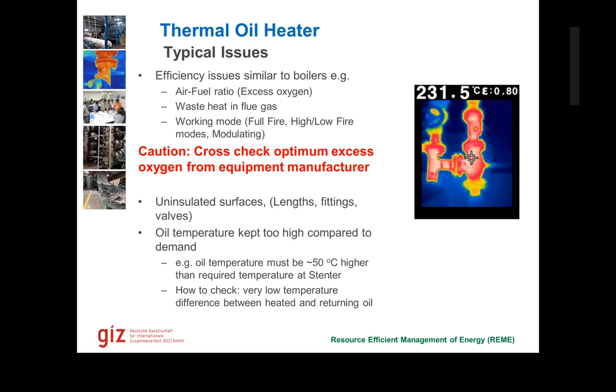Then talking about the air fuel ratio, managing air fuel ratio in a thermal oil heater is not as simple as in the case of steam. Anyways, whether it is a boiler or a thermal oil heater, it is important to contact the manufacturer or look at the design data. So recently, for example, for a thermal oil heater, we thought that we could bring down its excess oxygen from 8% to 3%. So we discussed with the manufacturers. They said that this equipment is optimized between 4% to 6% oxygen. So we suggest that you modulate it between 5 and 6%. So we had to revise our calculations based on that. So instead of suggesting 3%, we suggested 5% excess oxygen to this company.